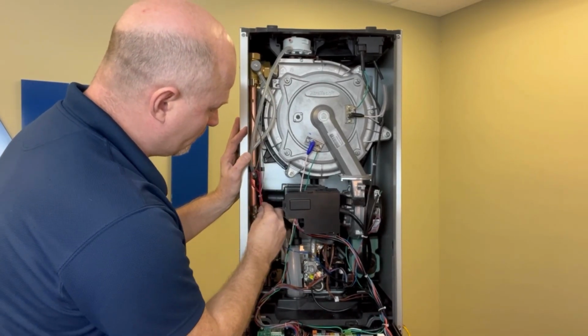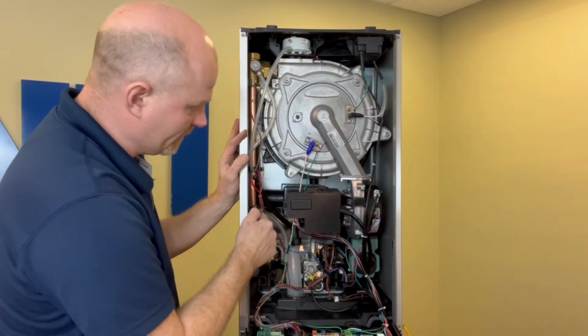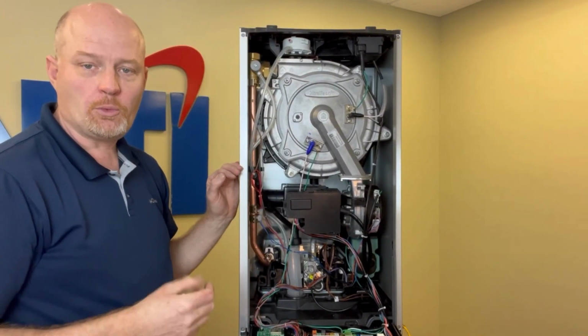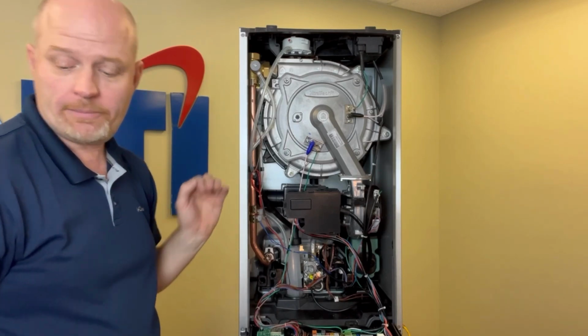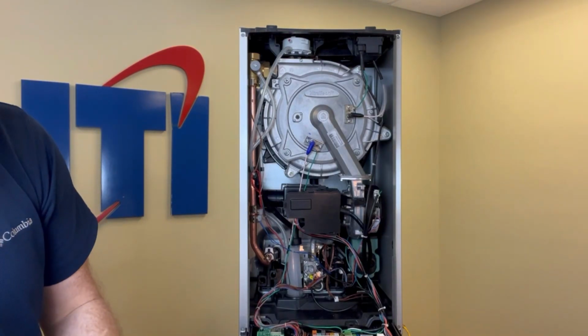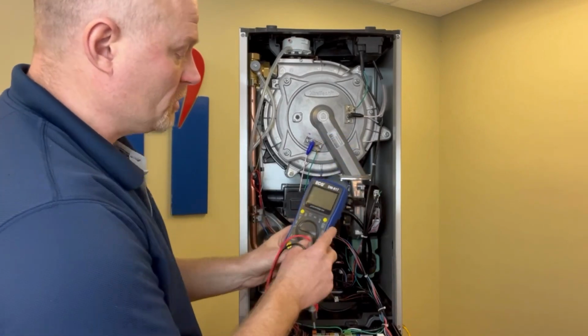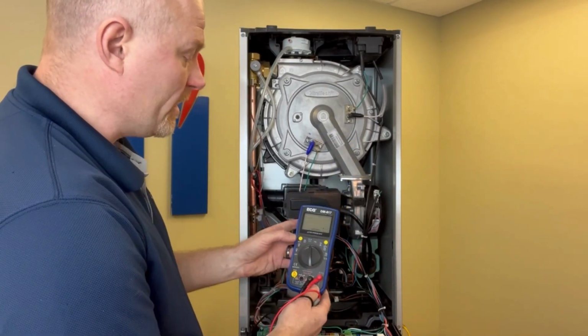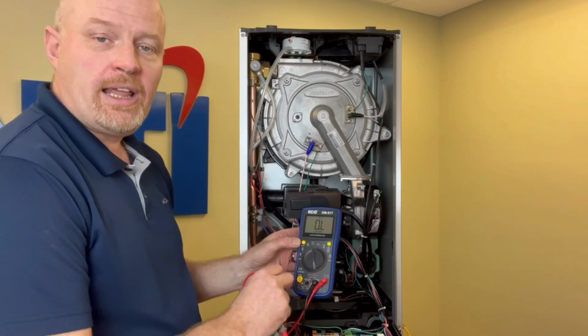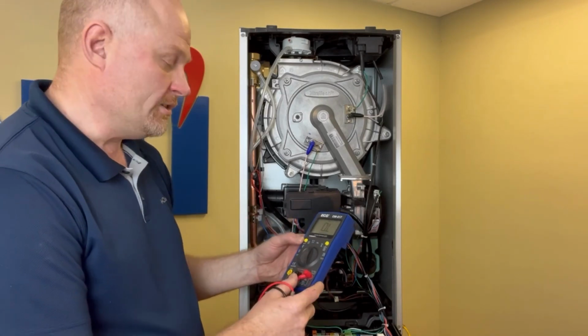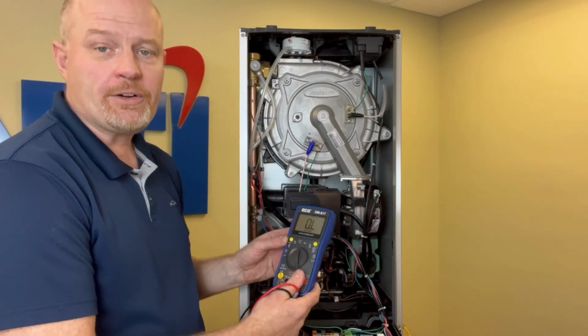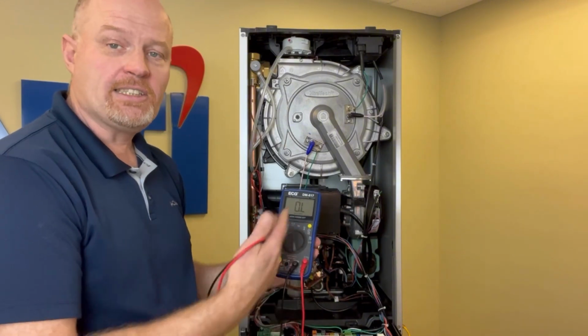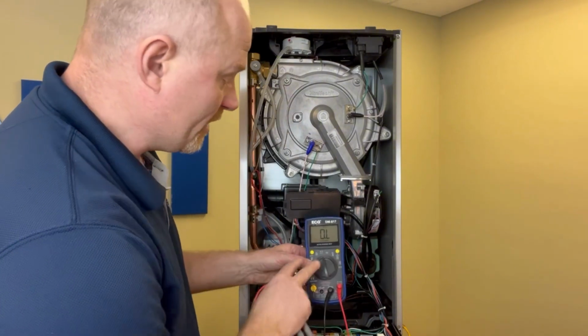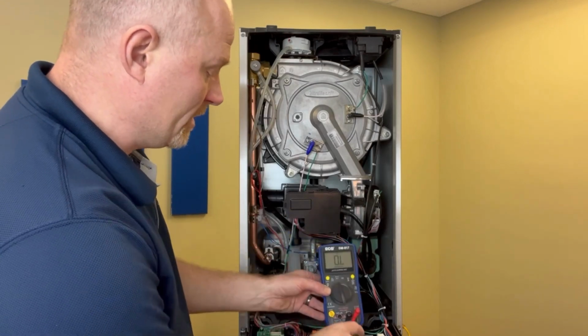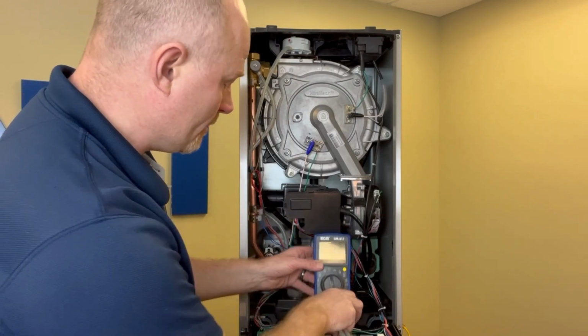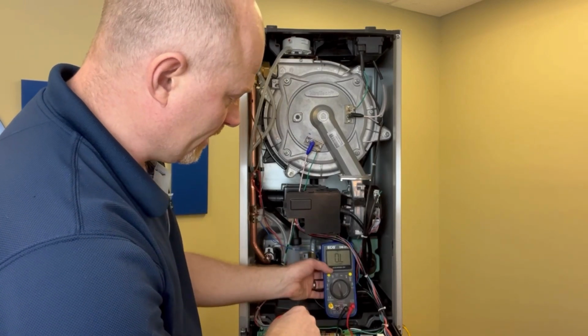Once you've established that potentially your problem exists, either in the sensor or in the wire harness, the next thing you're going to want to do is test these to ensure they're actually bad. To do that, grab your multimeter and set it to the kilo ohm range. Typically in the range of 20K is good enough for most temperatures. However, if it's very cold in the room you're in, you may need to set it into the mega ohm range. This one is an auto ranging meter, so I'm going to allow it to pick the range it wants. And I'll set that up there so you can see it.